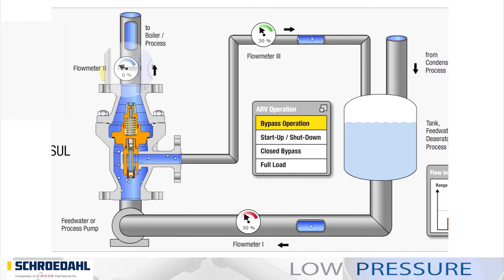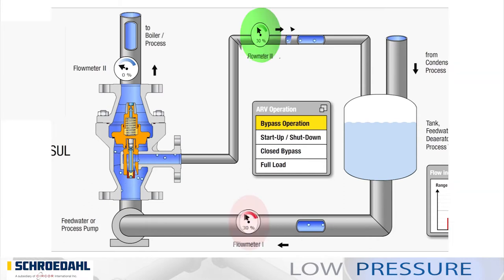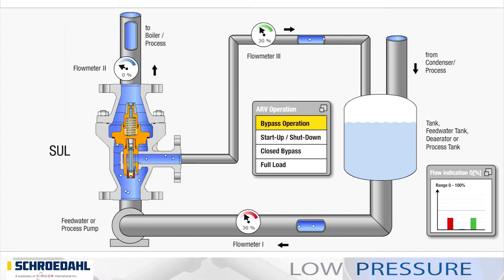Flow meter 2 displays 0% when no medium is being fed into the production process. The bypass of the automatic pump protection valve is in the fully open state. It feeds the medium through the valve to the tank and back to the pump circuit. Here, flow meter 1 and flow meter 3 show the same maximum flow rate value of 30%. The conical system, which is precisely adapted to the system requirements, closes the valve so that no medium is passed into the production process. Flow meter 2 shows 0%.